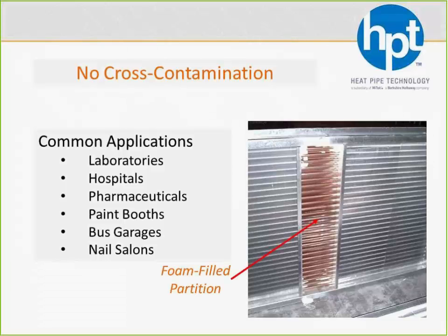You can use a heat pipe, and actually you'll find that we'll put a partition between those two air streams to isolate them, but we even go a step further at HPT and fill it up with a foam. This is very similar to the foam that's used as insulation inside air handler cabinets. We are not insulating anything, but when you pour this foam into that partition, it spreads out and hardens. Our tubes are going in between those end sheets right there, and even though we expand them, there are still some tiny holes around and cracks that might still be there when you put a microscope to it. So we just want to make sure that we fill in all those holes, and that's what that foam does for us.